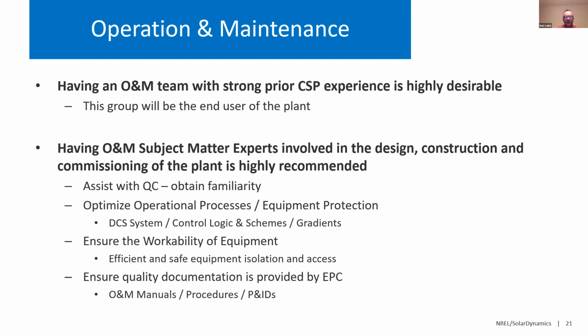Access and workability to equipment was brought up many times, especially by O&M groups, as being insufficient. Operators were often forced to access valves, for instance, that were impossible to access, and as a result, permanent scaffolding was not that uncommon. A bigger concern for the O&M people, and something they typically ended up doing later in the process, was adding the mechanisms for safe and efficient equipment isolation. It's very important in CSP to be able to efficiently evacuate systems so people can start working on them, and often that is not considered in the design.